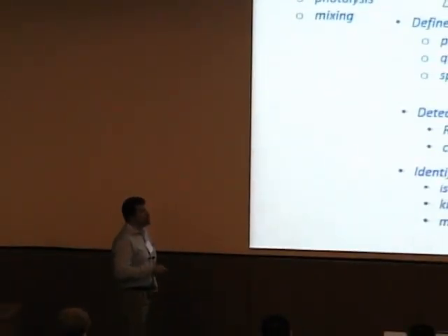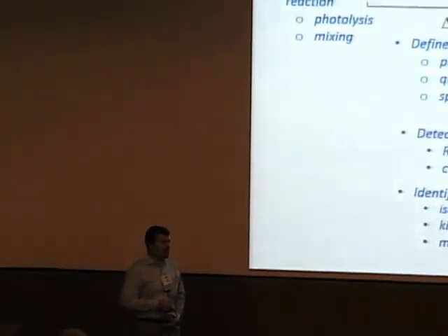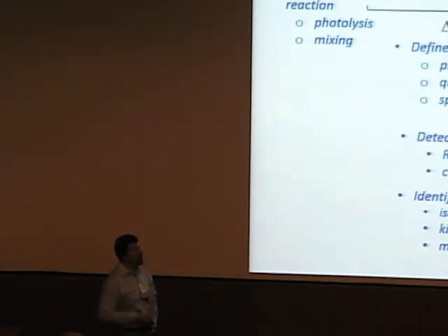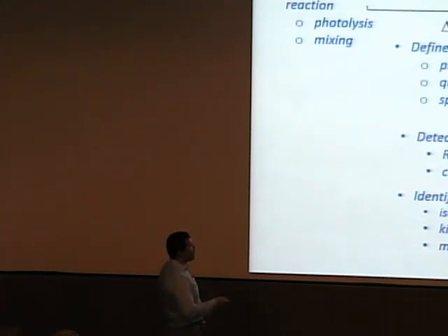Then you have to detect the species, as with any other technique. And in Raman, the difficulty is that the typical ratio of the number of excitation or Rayleigh photons versus the Raman scattering photons is about 10 to the 7th. So we're looking for very weak signals, very small signals, and that's for a single frequency. Of course, we want to spread it in a spectrum, so we have another order of 2, 3 of a loss if you're looking at the broad spectrum.